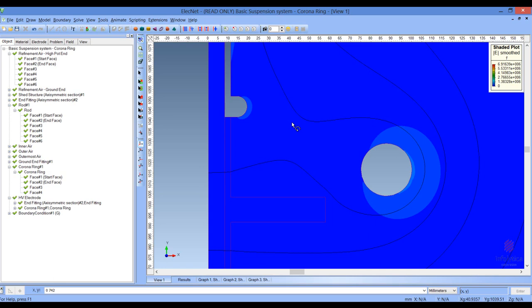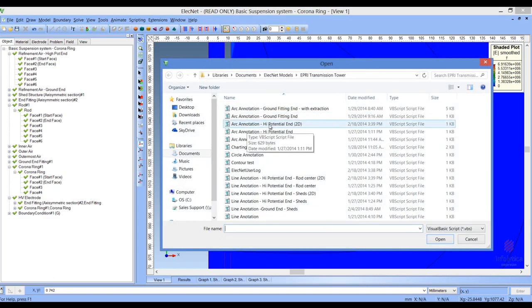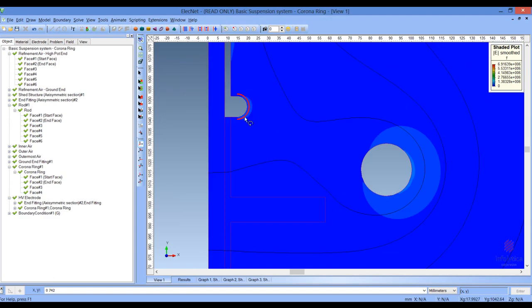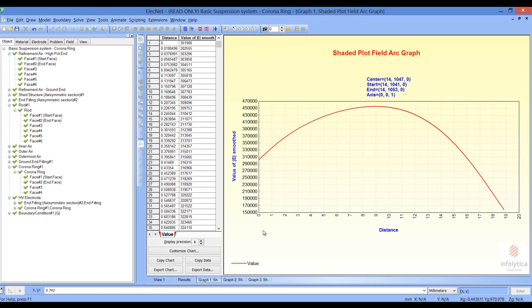The first contour will be the electric field stress along the outside of the fitting. Let me show you what that contour looks like again. We will extract the field around that contour, and the results are shown in this chart. Now in the EPRI report, this chart was not reproduced, so I cannot compare to the reported results in that report.